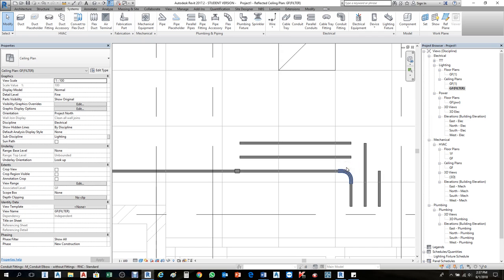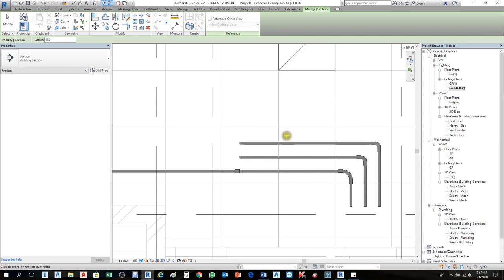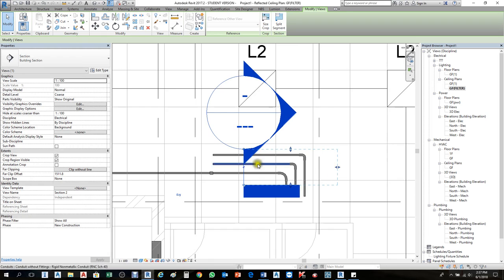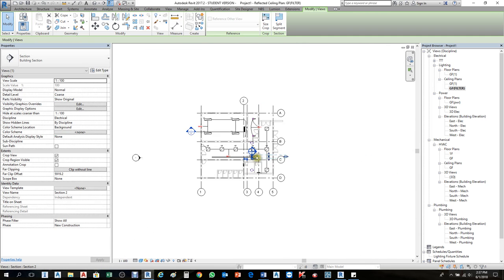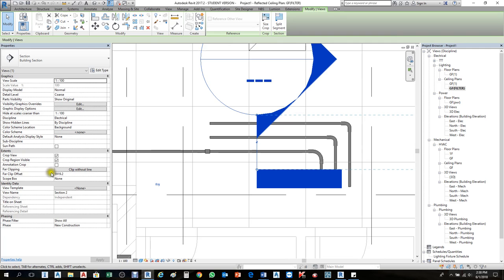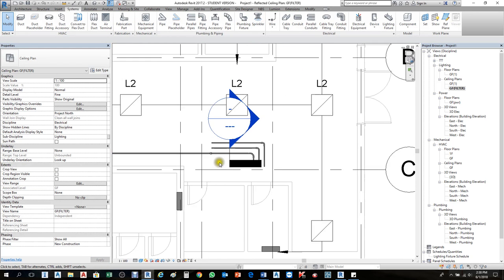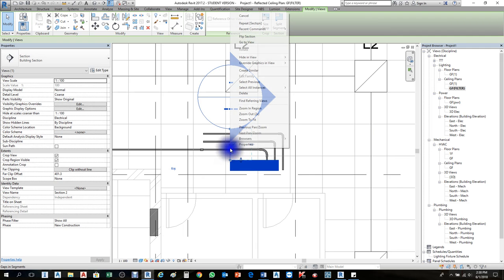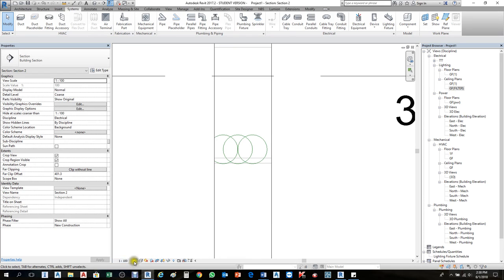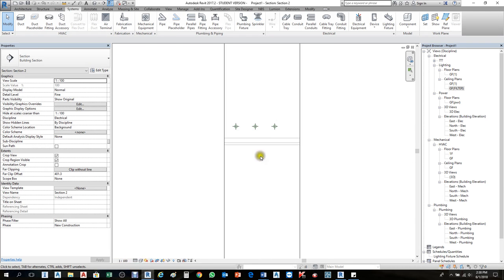The Trim command is very important and helps a lot. Now let's check in section view — create a section from the quick access control bar. Sometimes when you create a section it disappears far away. Click the section indicator, find Far Clip Offset — it may be 5919 — set it to 2000 so the section comes into view. Then make the view Fine to see the conduit clearly.